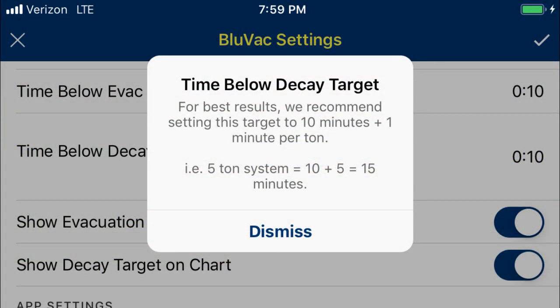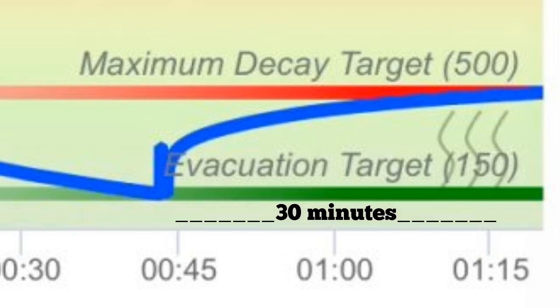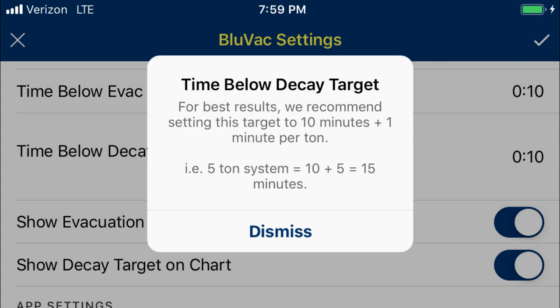When you go into the BluVac app, there is an information button next to the decay parameters, and it will tell you that when doing a vacuum decay test, you take 10 minutes and add one minute per ton. With a ton-and-a-half coil, that would mean 11 minutes and 30 seconds — and as you can see, we far surpassed that below decay. So theoretically, if we were following the directions of this app and all the vacuuming directions we've learned, we just had a successful, passed vacuum monitored by an app, put through a proper decay — on a leaking coil, leaking in two different spots.